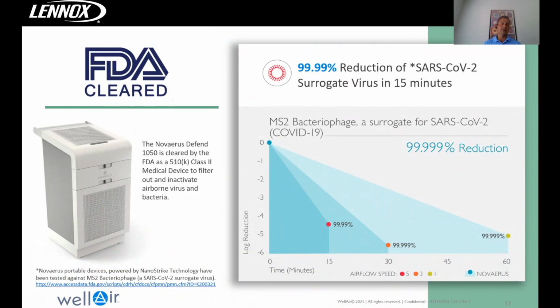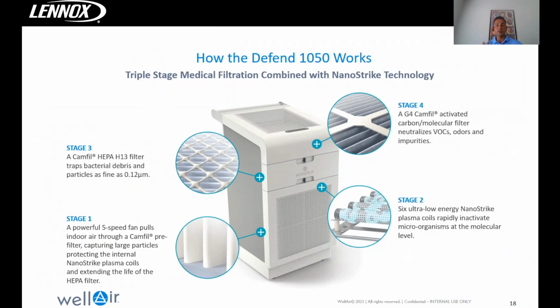The first one is our top-of-the-line, FDA-cleared 510K Class 2 medical device to filter out and inactivate virus or bacteria. This one is a little different—I just talked about HEPA filtration and why I wouldn't position it in certain environments. Our Nanostrike technology is outstanding at killing anything alive in the air, but similar to ionization, it doesn't deactivate TVOCs or get rid of particulate matter; there's very little effect on that. Because of that, the Defend 1050 has both a HEPA filter and a carbon filter to capture particulate matter and keep TVOCs out of the space. This unit comes in 5 speeds, the highest being 533 cubic feet per minute.